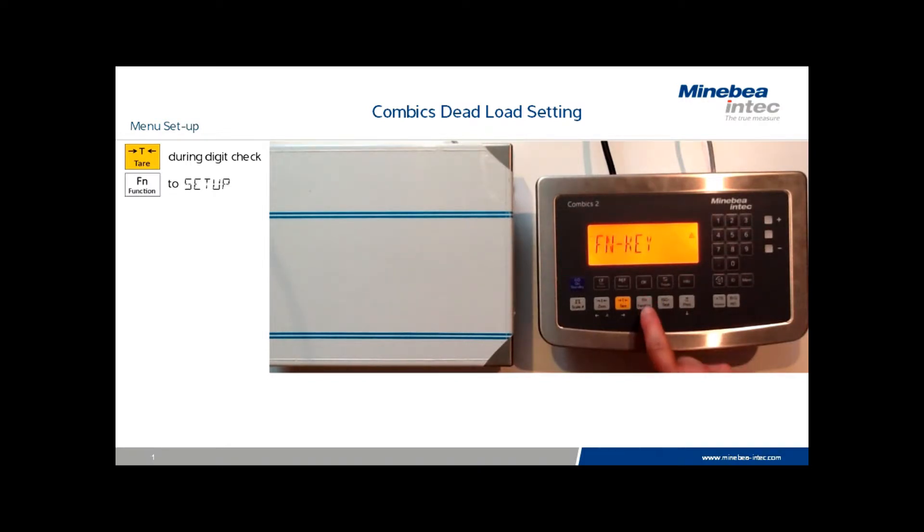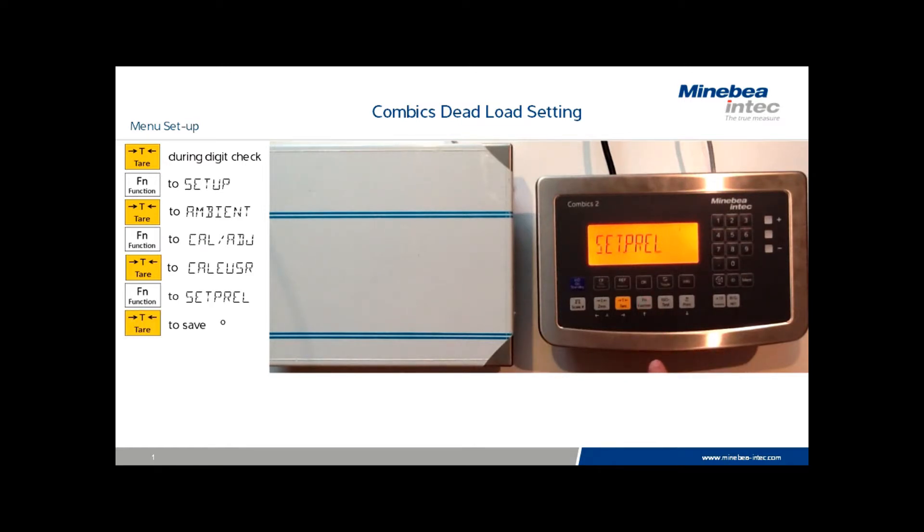Once you've accessed the menu, press the function key to scroll to setup. Press the tare key until you see the word ambient on the display. Now press the function key several times, scrolling through several menu options until you see the word cal adjust. Press the tare key to get into the calibration menu and scroll with the function key until set preload is displayed. Hold the tare to exit to the weighing mode.